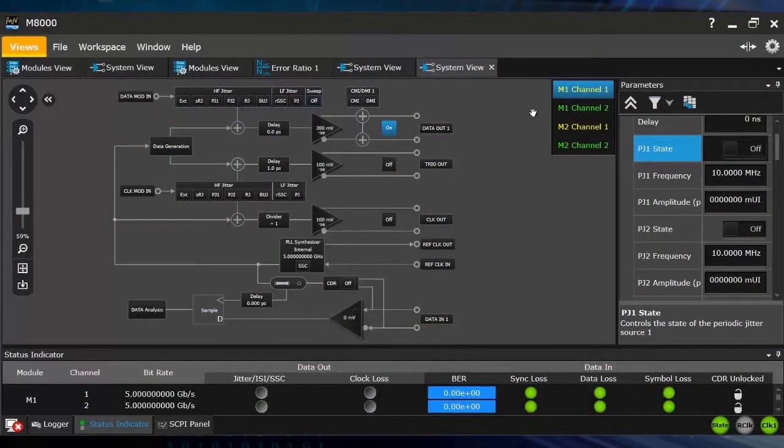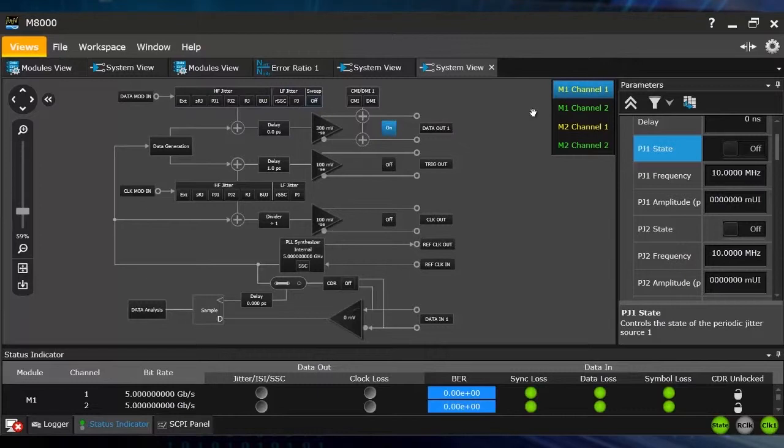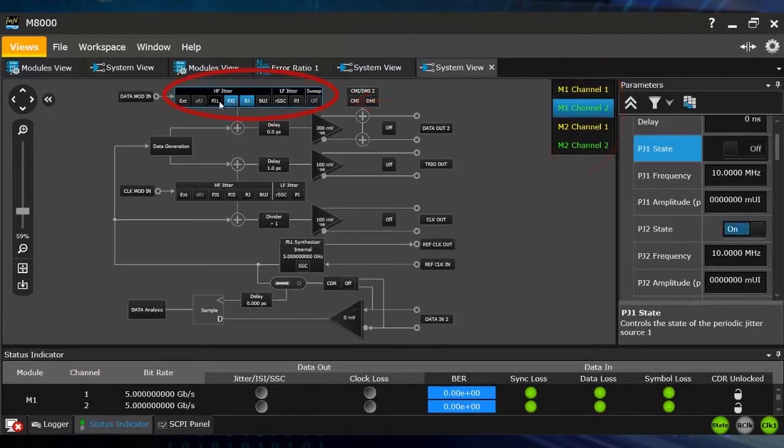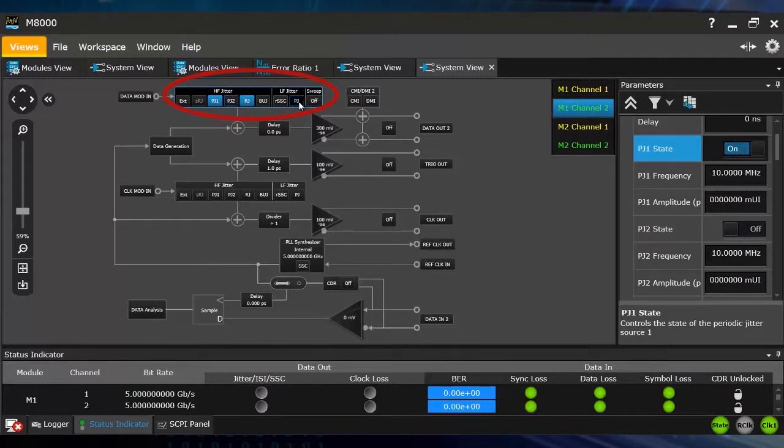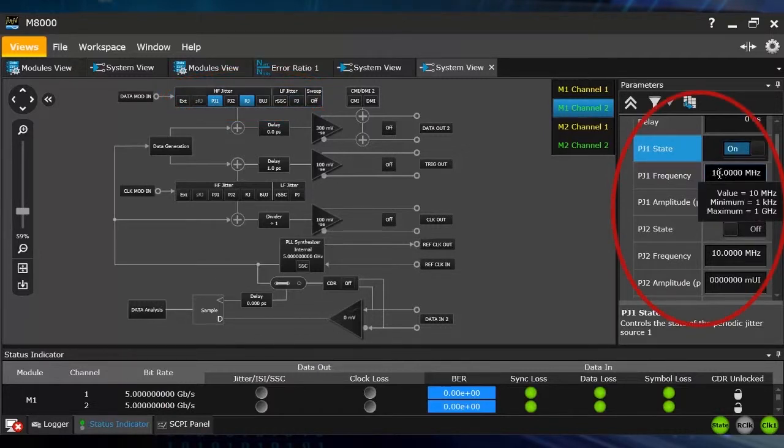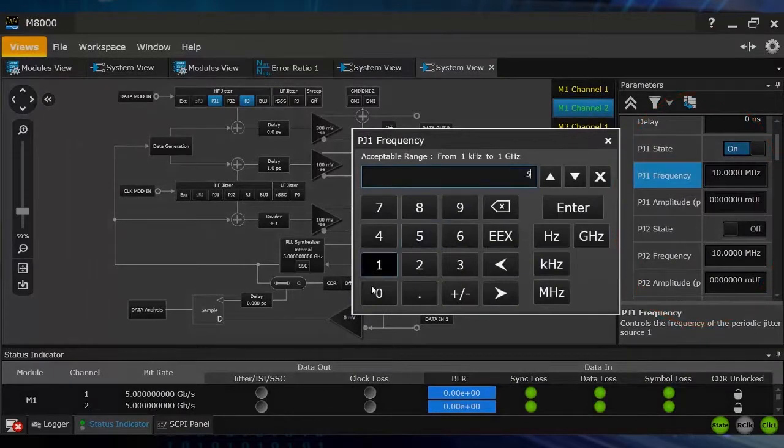So now I want to show you the jitter injection capabilities of the new J-BERT M8020. Each data channel has jitter sources that can be turned on and off individually. The jitter sources are calibrated.